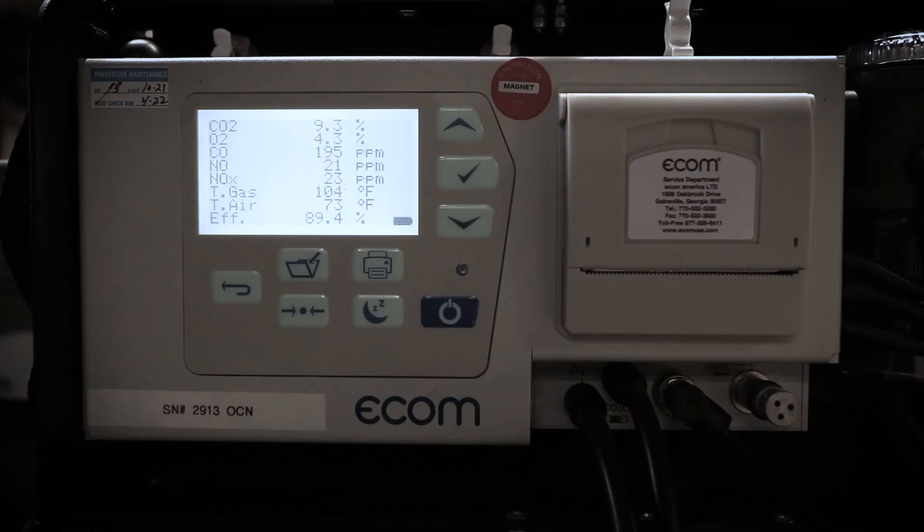For natural gas units, we want to set the CO2 on high fire between 9.1 and 9.3%. On propane units, the CO2 needs to be between 10.1 and 10.5%. Additionally, make sure the CO level is less than 200 parts per million.